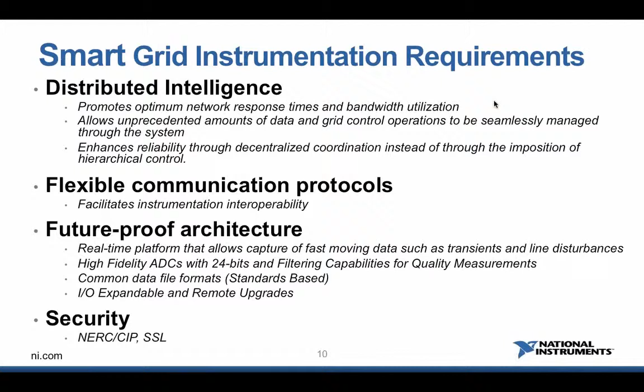The other important point is security. As more and more computers control, manage, and monitor the grid for us, security becomes a huge concern. The last thing we want is a bad-intentioned person taking control of the grid and doing bad things with it. So we need to comply with standards like NERC CIP. NERC stands for North America Electric Reliability Corporation, and CIP is Critical Infrastructure Protection, which have an extensive library of standards and recommendations for protecting your devices and instruments.